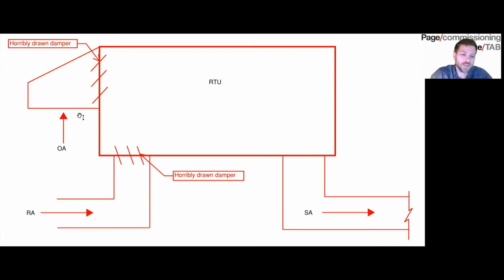So one way is you can close your return air damper and open up your outside air damper fully, right? And then you would back down your supply airflow to where you would equal your outside air for this unit. So typically your schedule will list your minimum outside air that's required for ASHRAE 62.1 for the building or the space that it's serving. And then you'll back down your supply airflow until you hit that. And once you get there, then you can just simply traverse your supply duct. So just pick a spot where you get a nice straight run, traverse your supply, and then you'll use that to calibrate your outside air flow station.